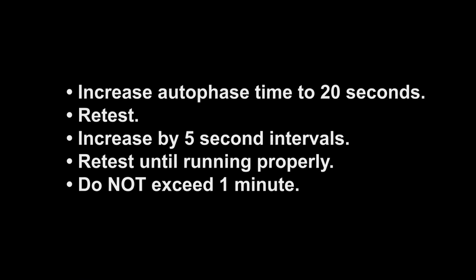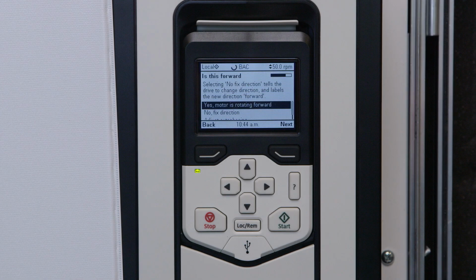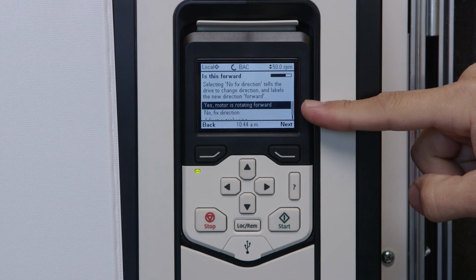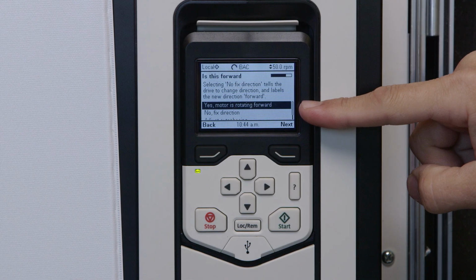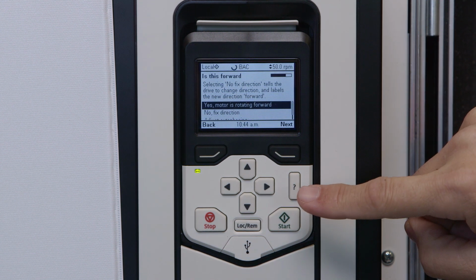If the motor is still cogging or not turning at all, continue to increase time in 5-second intervals and rerun the direction test until the motor is running properly. Do not exceed 1 minute. Once the fan is running properly and spinning in the correct direction, highlight the message, "Yes, motor is rotating forward," and then press Next.